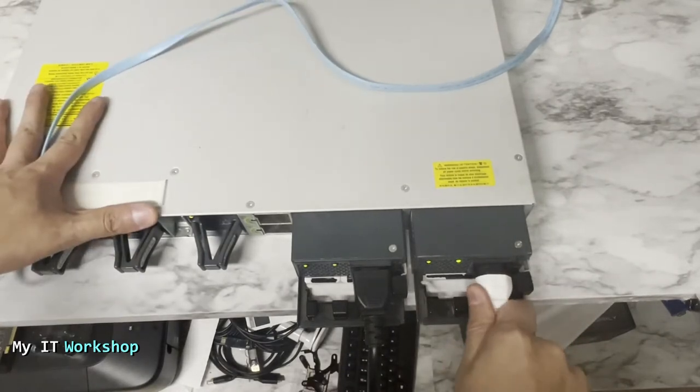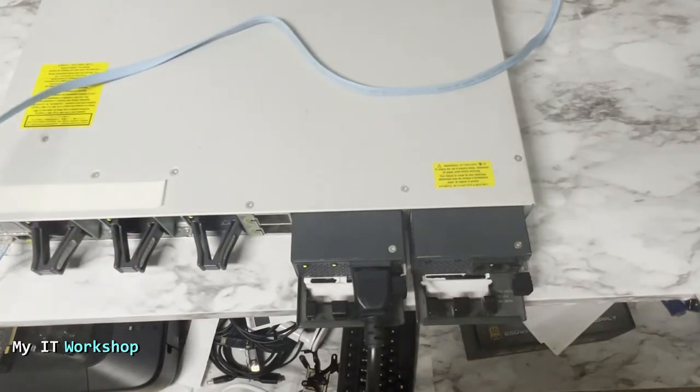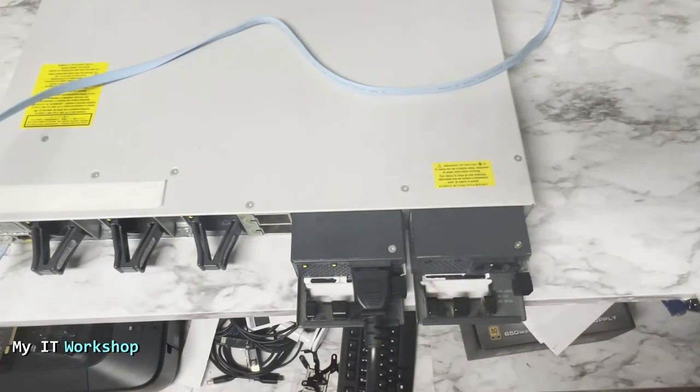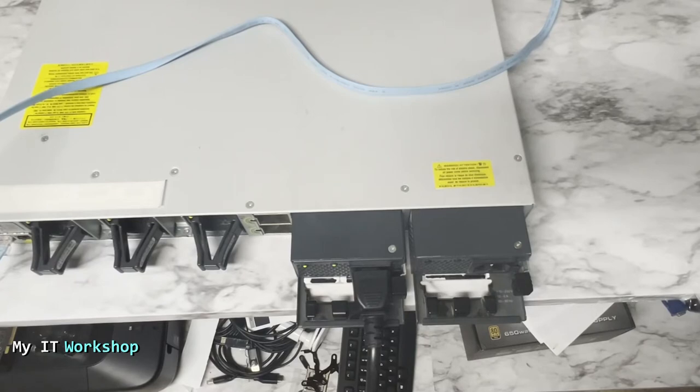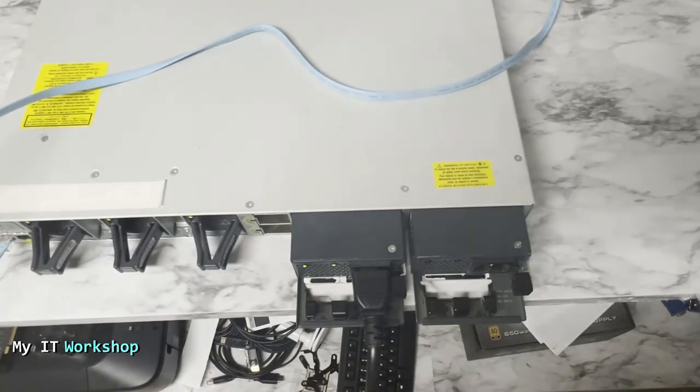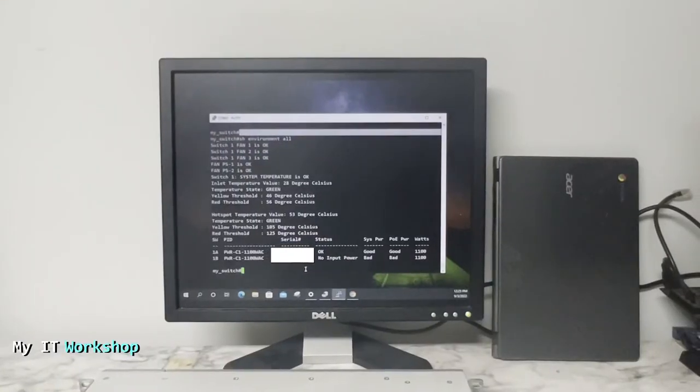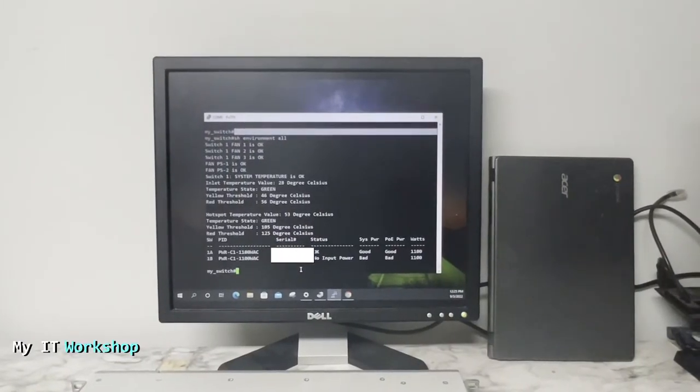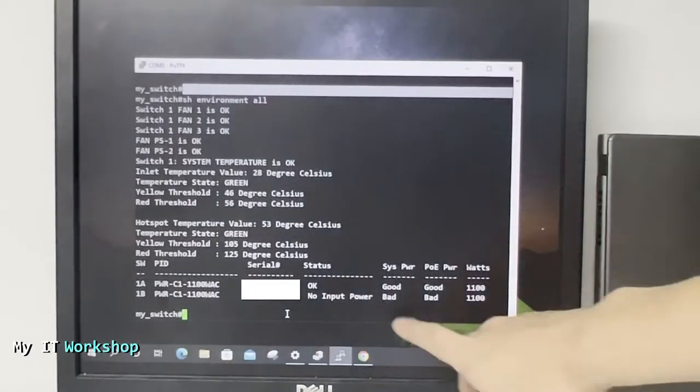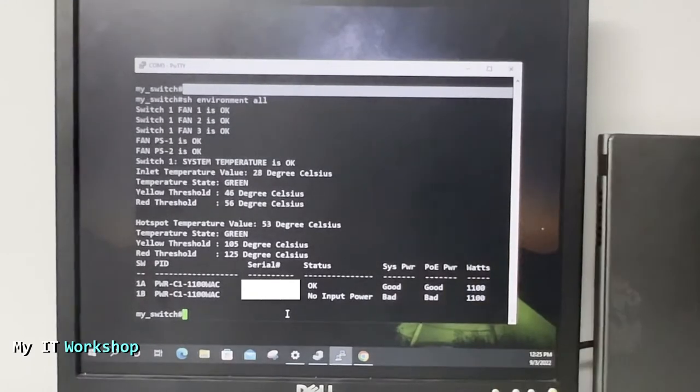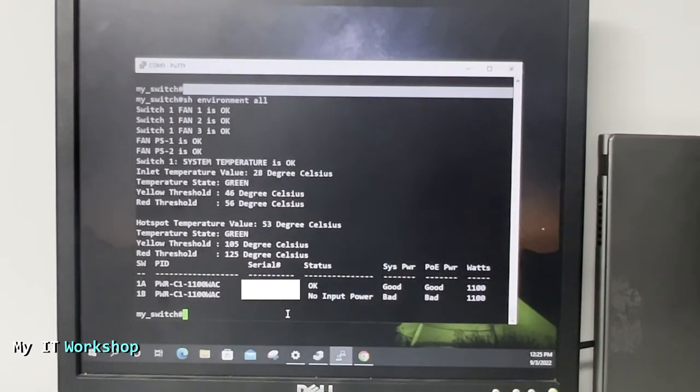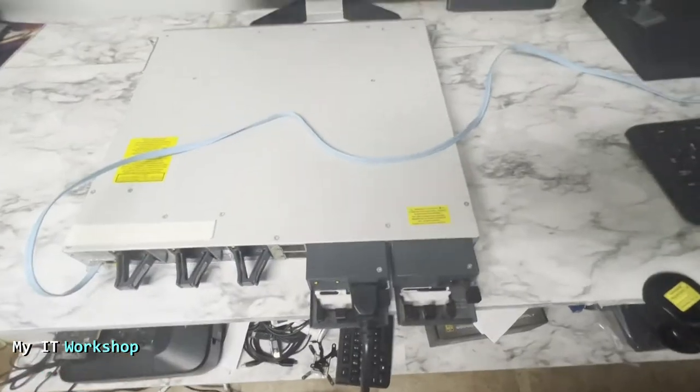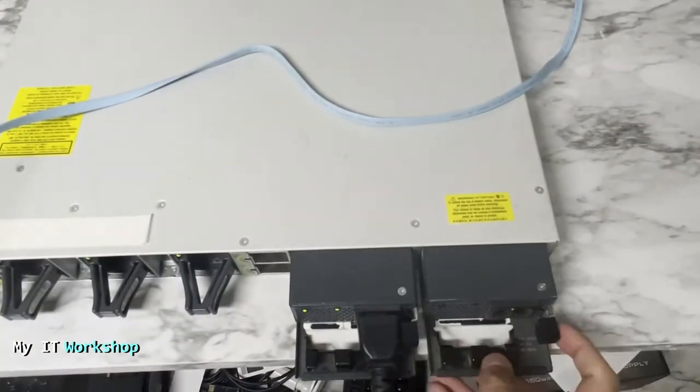Now I'm going to disconnect the one on the right like that. The power supply is dead now, however the switch is still working because of the other power supply. Now allow me a few seconds and we'll go back to the console. As you can see, for power supply B the status is no input power and the system power is bad because it's not receiving power.